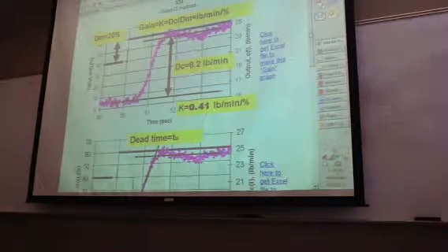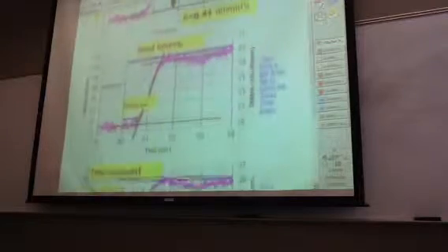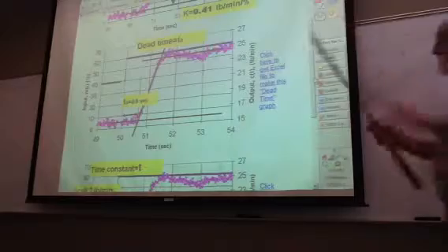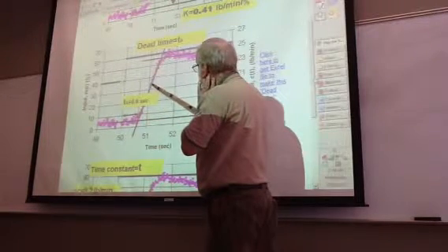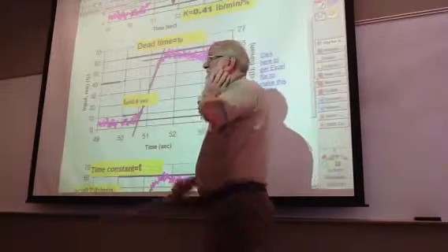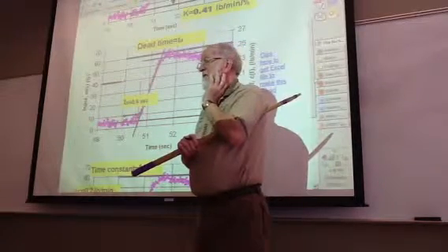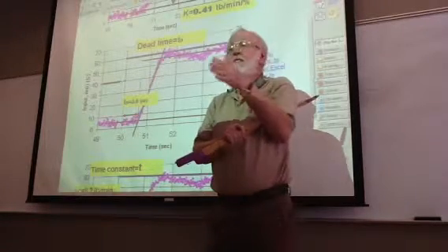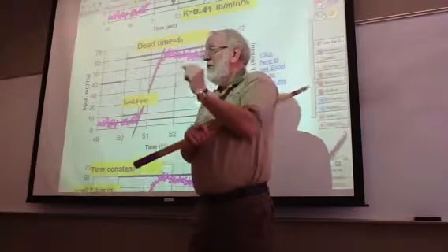And how many parameters do we want to get? Three. So here's the second one. It's called dead time. To do that, we draw a straight line wherever is the steepest slope of the output curve. This takes eyeball. This does not mean you go into Excel and ask it to tell you where the steepest point is. That's pain. Use your eyeballs.